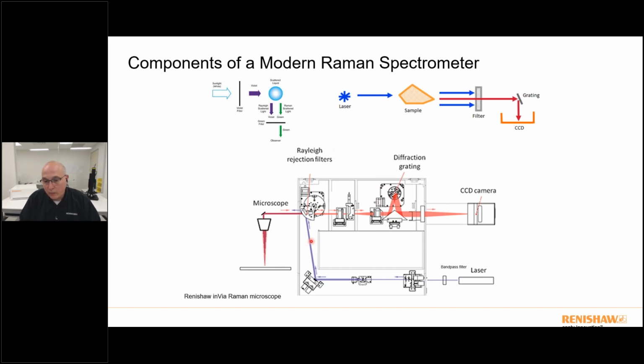In the case of a inVia Raman microscope, this is what the internal guts of the instrument look like. We'll have a laser source, maybe some sort of bandpass filter. We'll deliver that light, conditioning it in some manner towards the Rayleigh filters, which reject the laser light and couple it into the microscope, where we're using objectives to be able to illuminate the sample. We're collecting all of that light back into the microscope through 180-degree backscatter collection. And then that light is presented towards the spectrometer where it's dispersed onto the CCD camera. So this is the fundamental design.